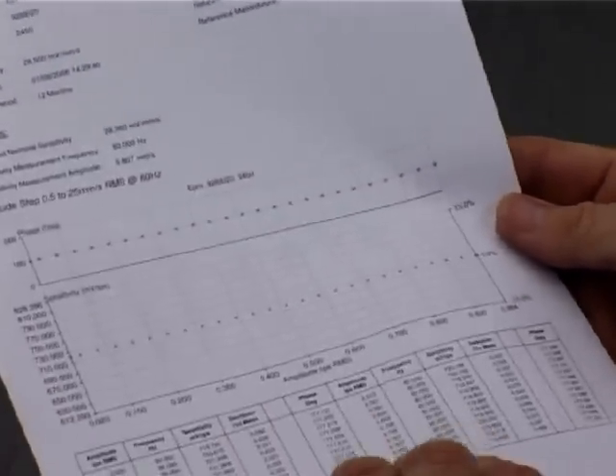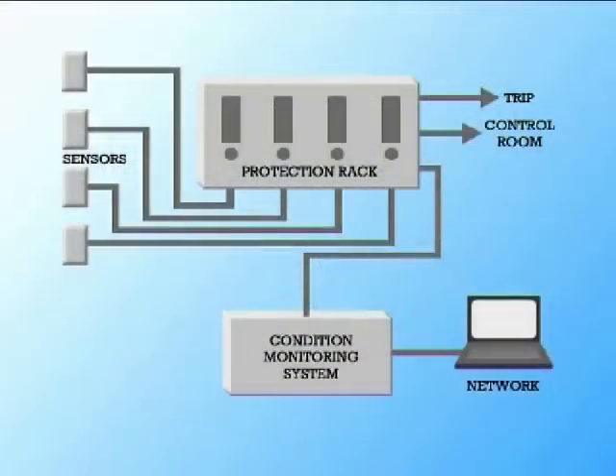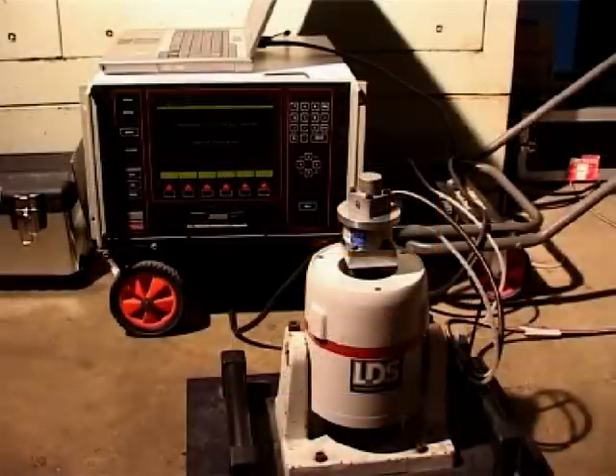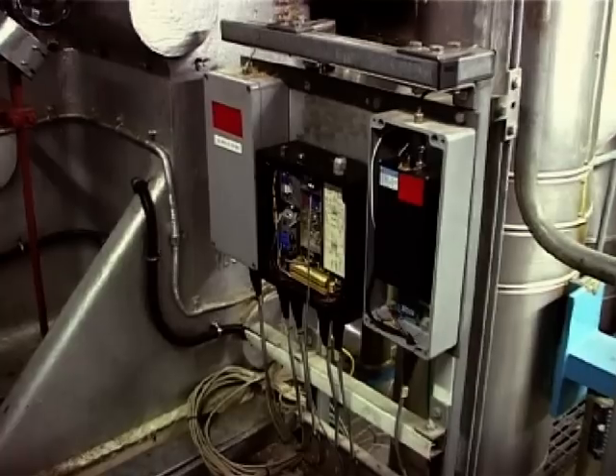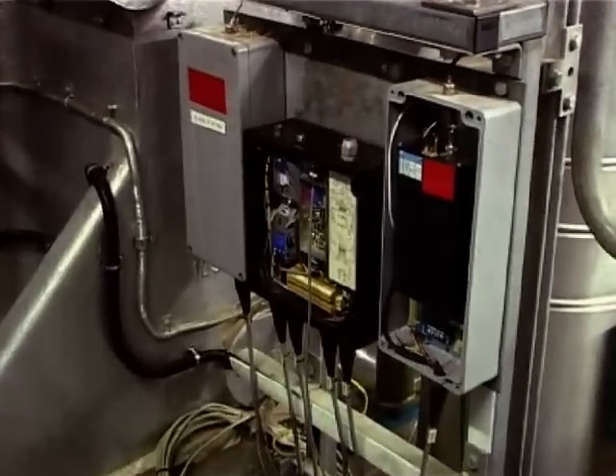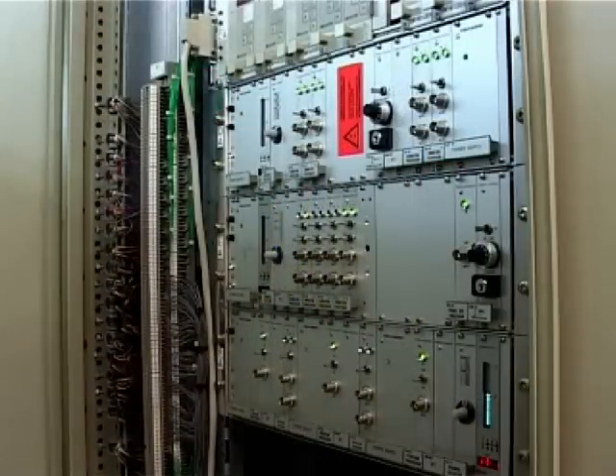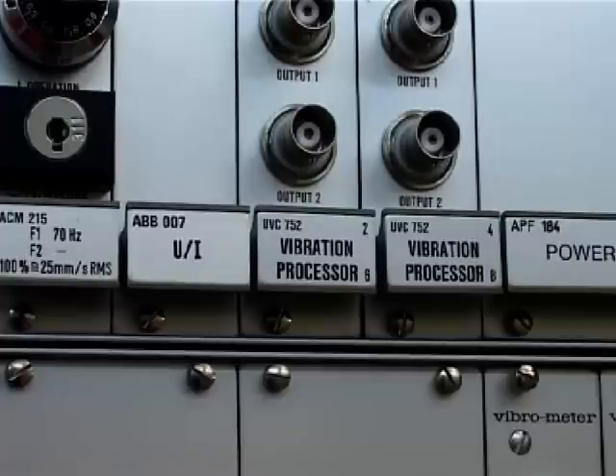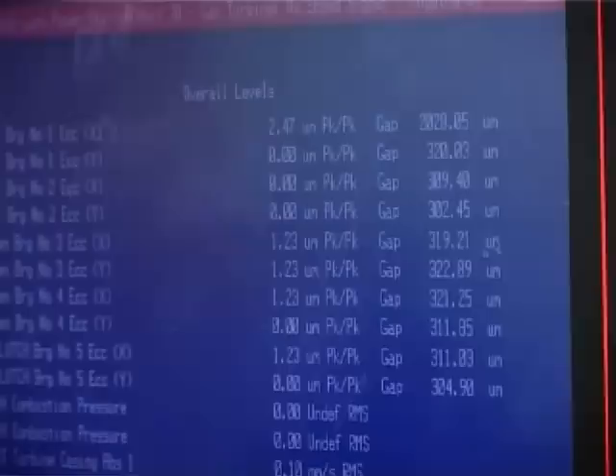As well as separate transducers, the TransCal system allows any isolation amplifiers, integration stages, filters, trip alarms and control room displays to be traceably calibrated for each channel as a complete measurement chain. In this procedure, the transducer remains mounted on the shaker table, but it is reconnected to the plant instrumentation. A new calibration test is recalled from the database in order to calibrate the plant instrumentation in its normal operating vibration units, usually velocity or displacement.